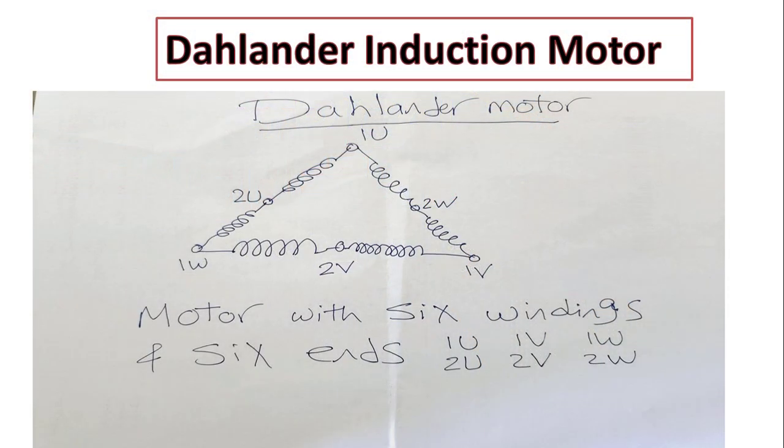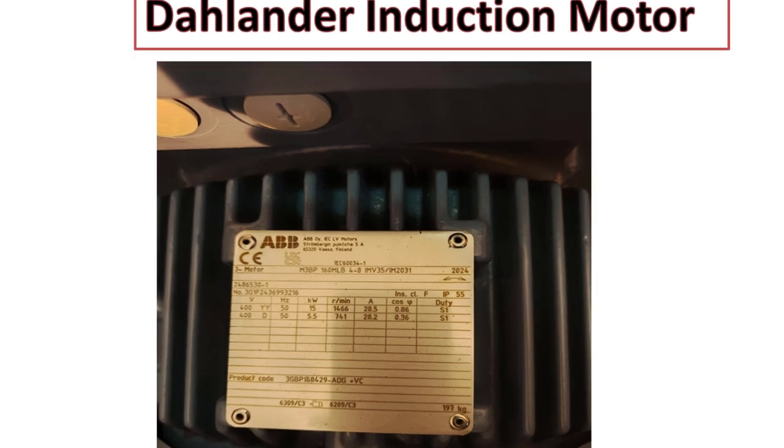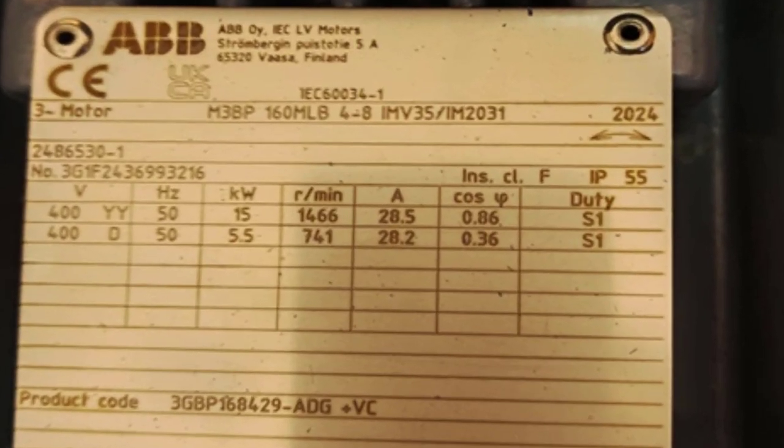Here in this special three-phase induction motor, as you can see, we have six windings with six different ends: 1U, 1V, 1W, 2U, 2V, 2W. In this motor nameplate you will find that this motor could have two different speeds. First speed is 1466 RPM in case of star-star connection, and the second speed is 741 RPM in case of delta connection.